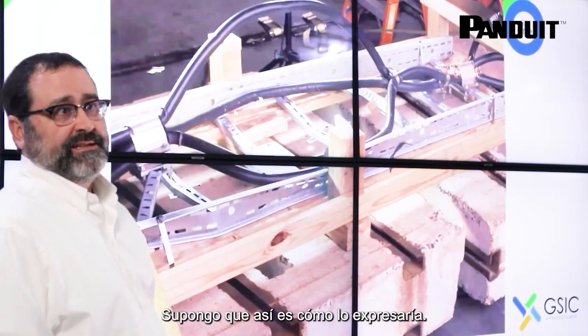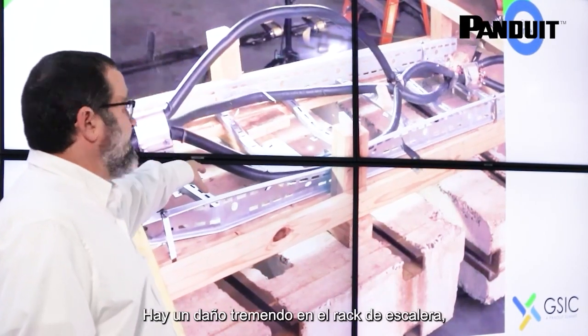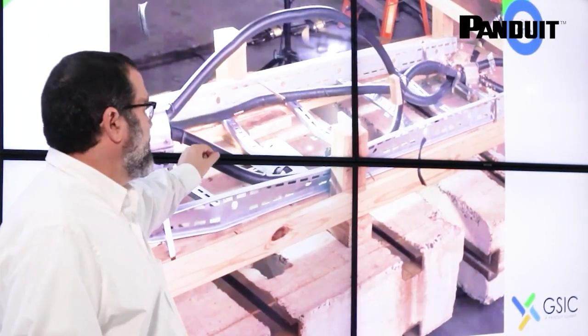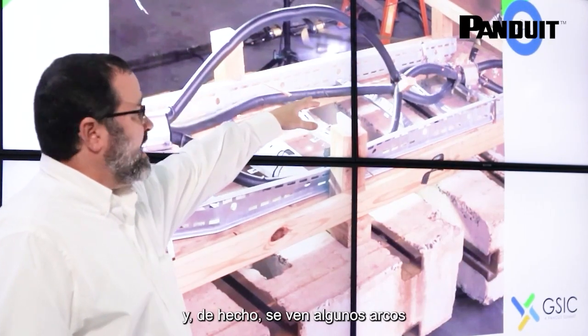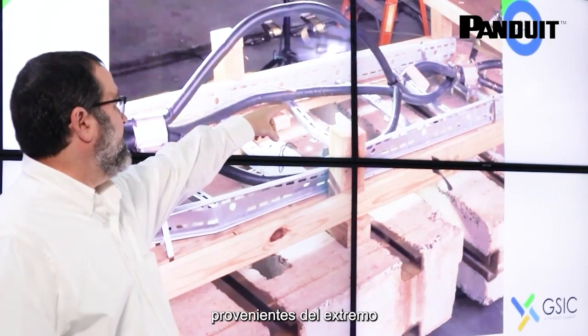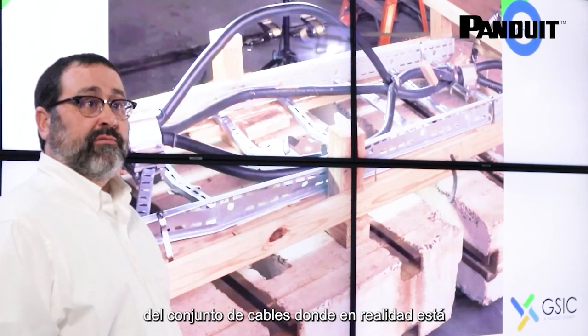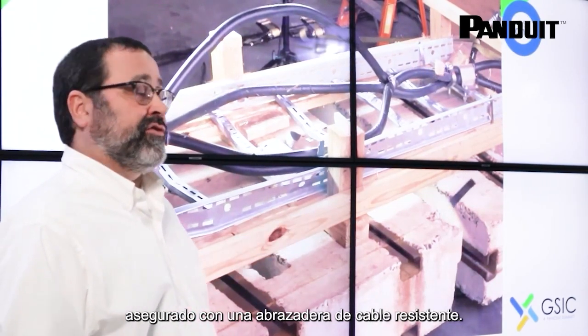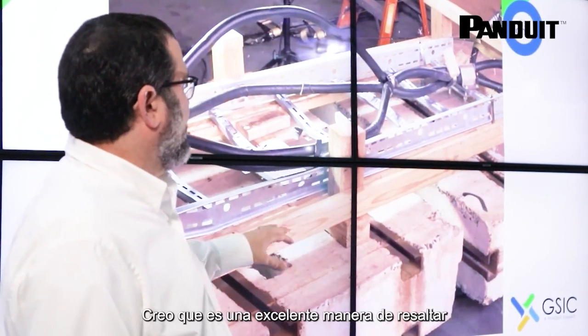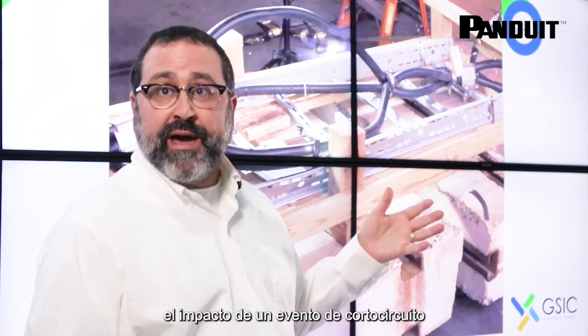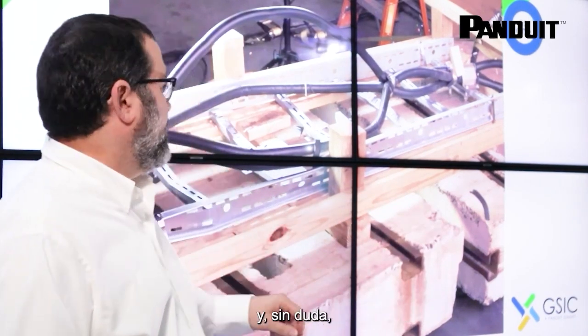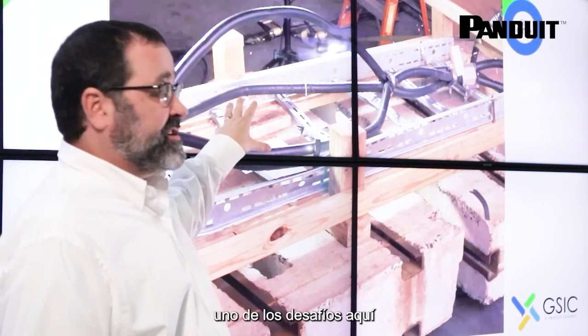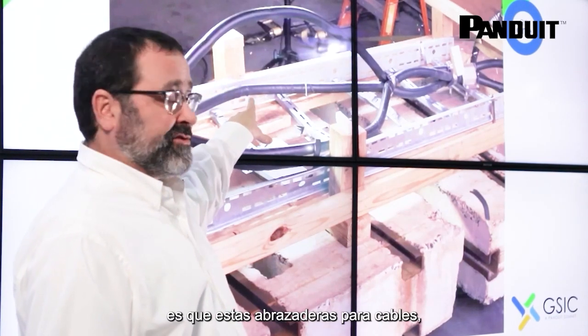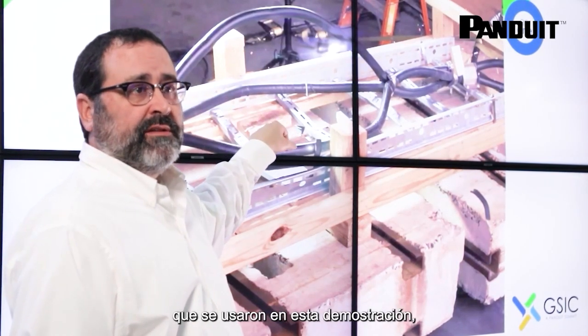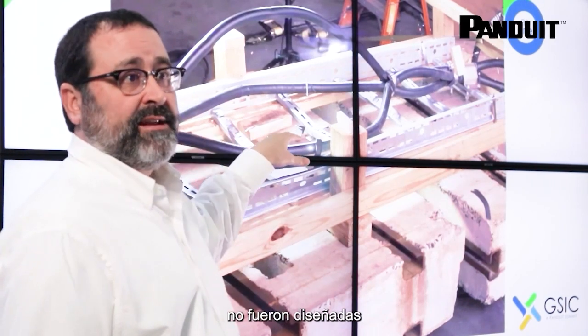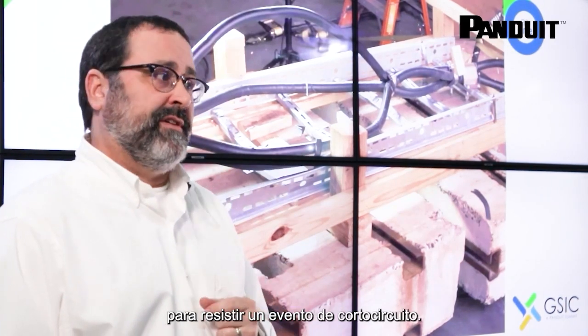The straps explode, I guess is how I'd phrase it. There's tremendous damage to the ladder rack. The cables are permanently deformed, and you can see some arcing from the end of the cable assembly where it's secured with a strong cable cleat. This highlights the impact of a short circuit event. One challenge is that these cable straps, the stainless steel ties used in this demonstration, were not designed to withstand a short circuit event.